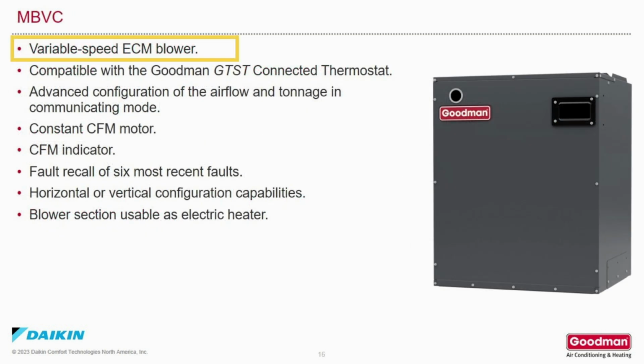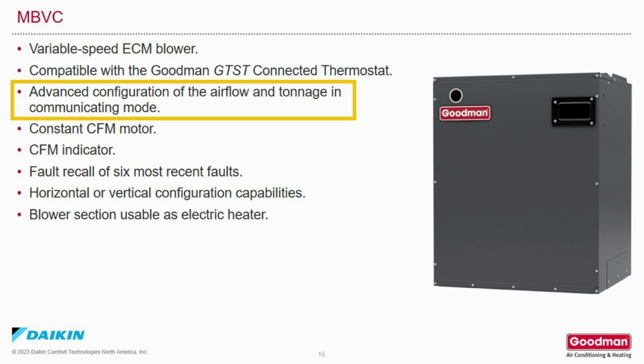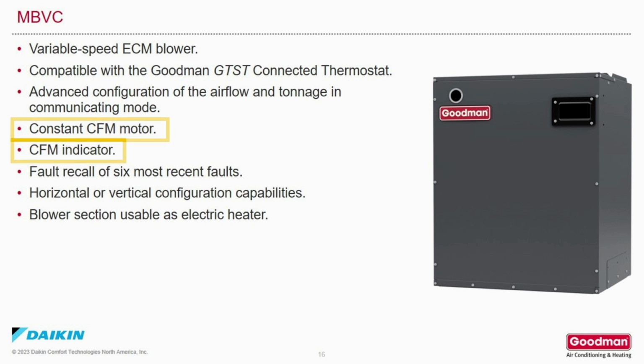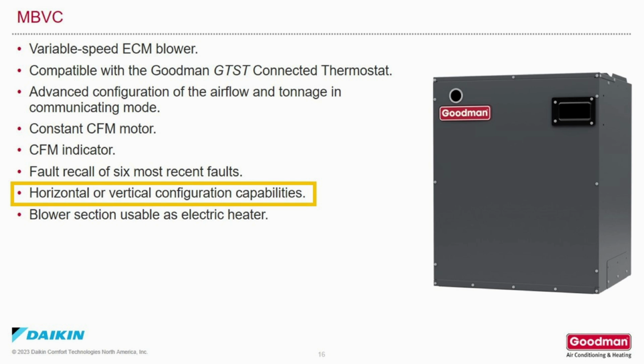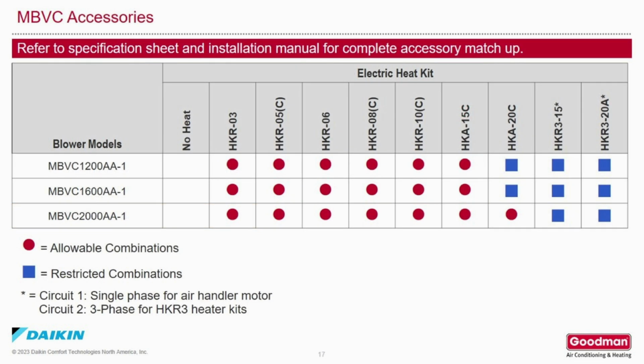The MBVC is a variable speed blower with an ECM motor, compatible with the Goodman GTST connected thermostat, advanced configuration of the airflow and tonnage in the communicating mode, constant CFM motor, CFM indicator, fault recall of the 6 most recent faults, horizontal or vertical configuration capabilities, and the blower section is usable as an electric heater. Here is a list of some of the allowable and restricted electric heat kits available for the MBVC air handler. Please refer to the specification sheet and installation manual for a complete accessory matchup.